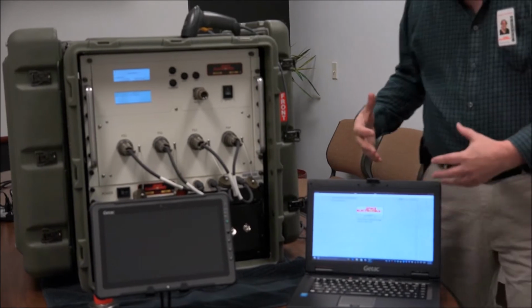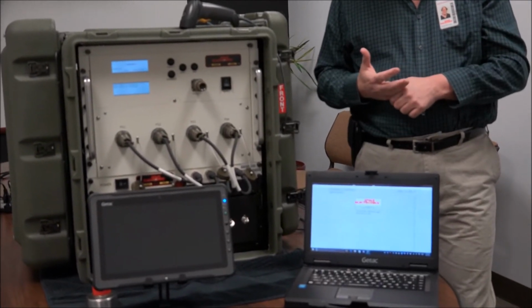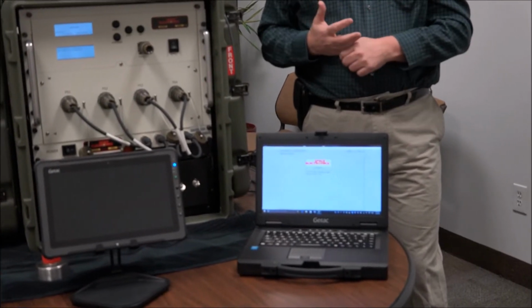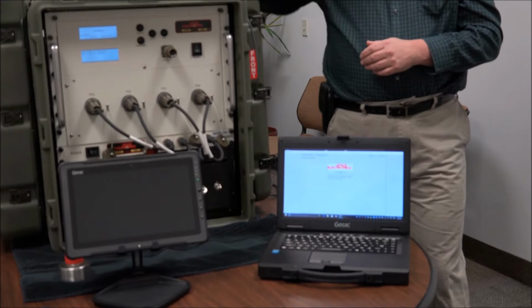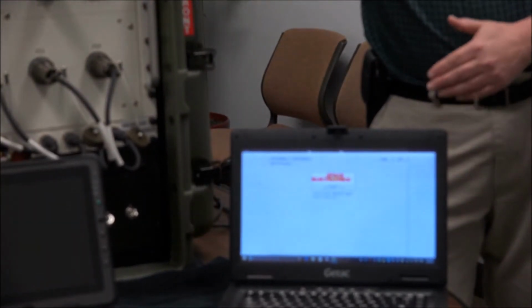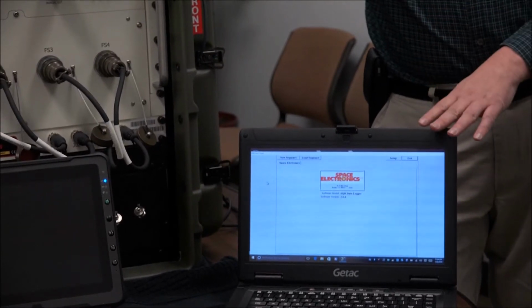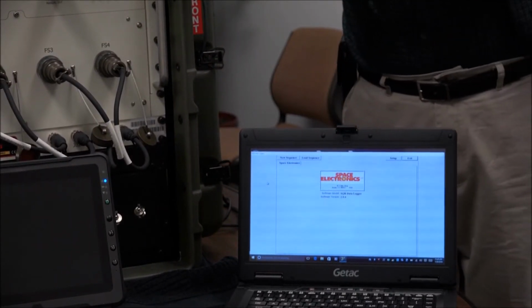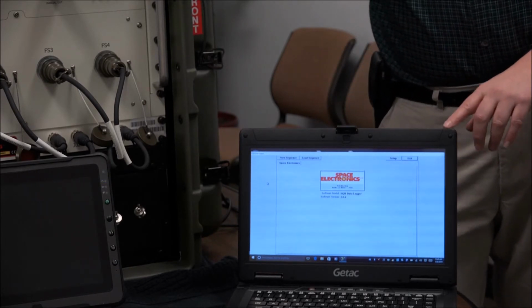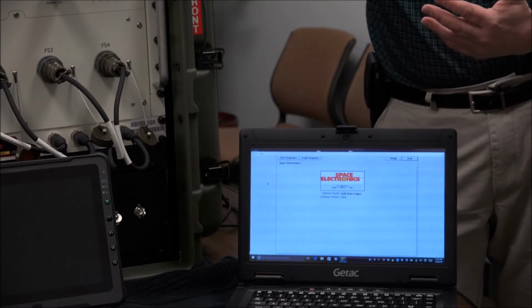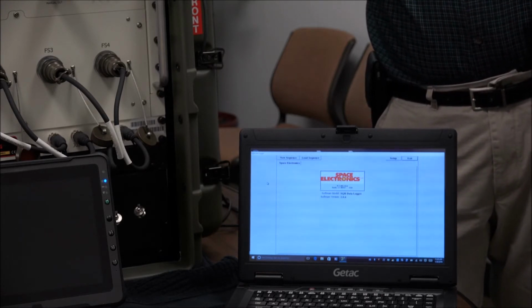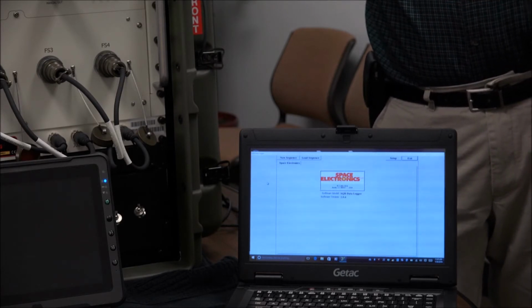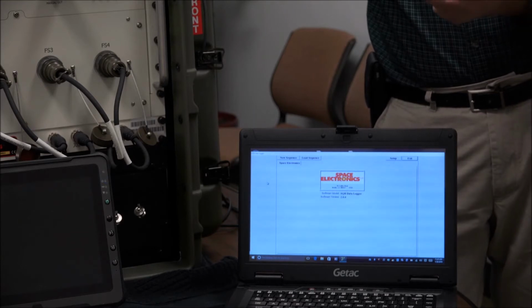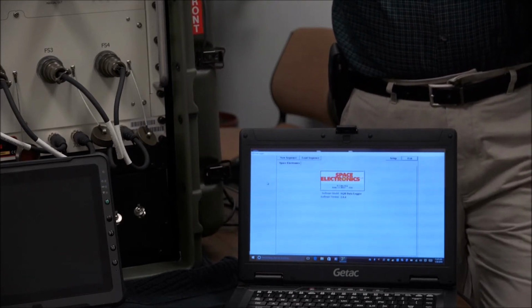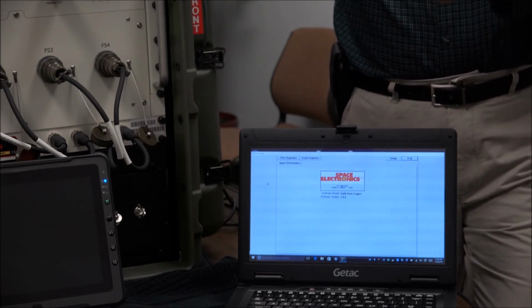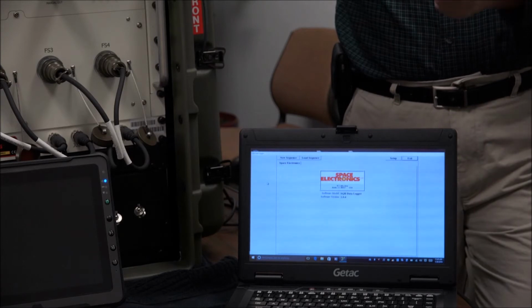So this software allows you, as an engineer, to define the sequence. It's a CSV file. The CSV file has its own command structure and it's defined for you, so it's very easy to use. The commands include defining whether it's going to be an automated test or a manual test. The manual tests are used with our PTU units. The automated tests are used with the SQB units. You can also define what circuits are being tested. You can define the name of the circuit, the two test point wires you're connecting to, the type of test, whether it's voltage, diode, or resistance, the range of the test, whether it's a 100 millivolt or 2 volt voltage test, or whether it's a 20 ohm to 2 meg resistance test.